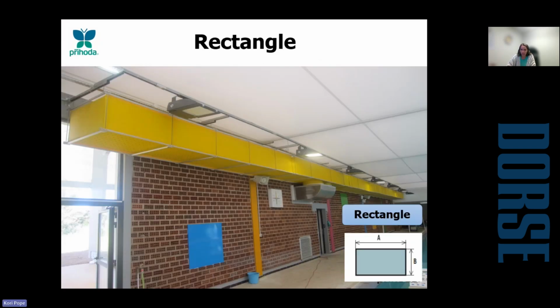We have our rectangular ductwork. So the cool feature with rectangular duct is it can be used for positive and negative pressure applications. So in this specific image, we are in a swimming pool where they had a lower ceiling. So doing your traditional round just wouldn't have worked for clearance, as well as they were looking for a little bit of cost saving options. So we're able to do fabric instead of them having to do stainless steel metal here.